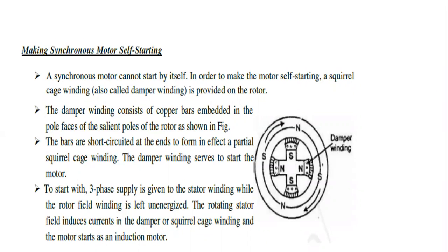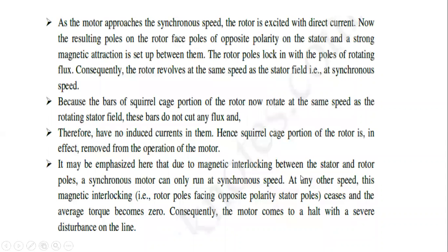The rotating stator field induces current in the damper or squirrel cage windings. The motor starts as an induction motor. That is the procedure for the motor in the self-starting mode.